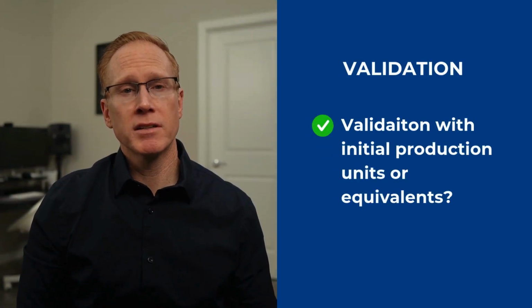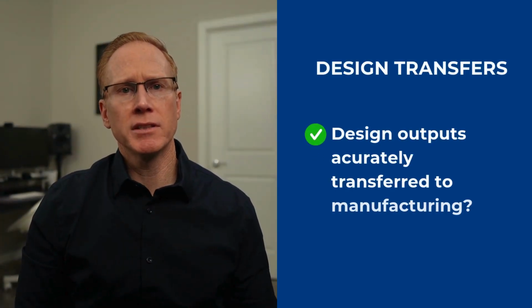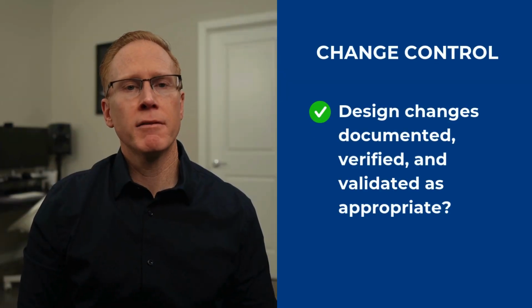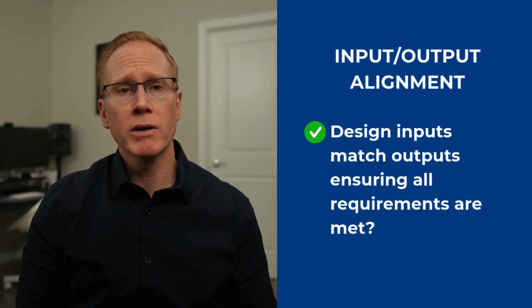Validation. Was design validation completed using initial production devices or their equivalents? Design transfers. Were design outputs accurately transferred to manufacturing? Change control. Are design changes well documented, verified, and validated? Input-output alignment. Do design inputs match outputs, ensuring all requirements are met?